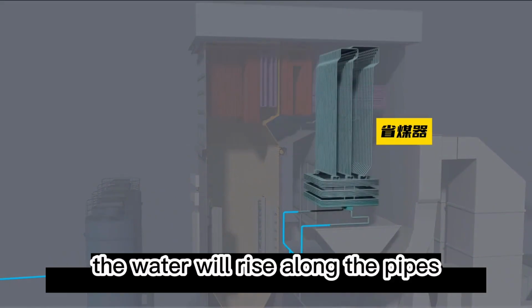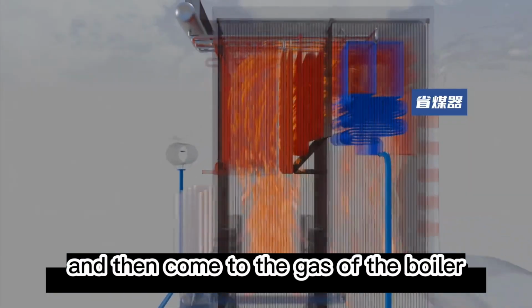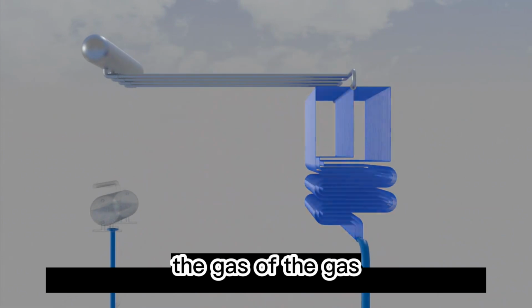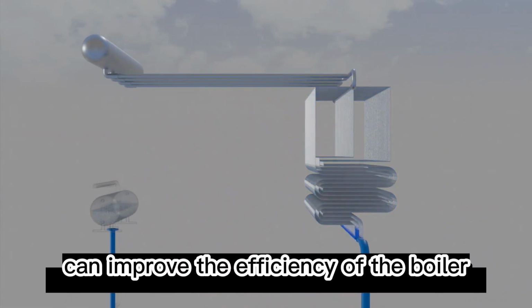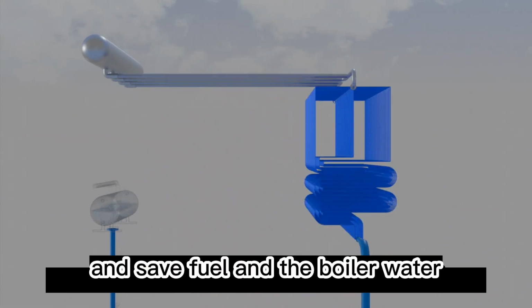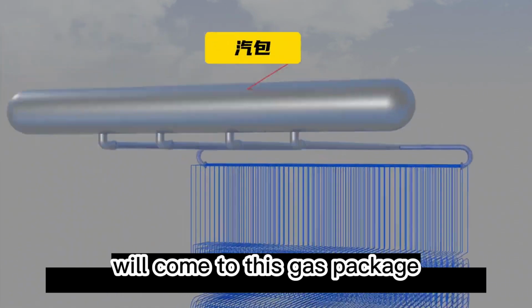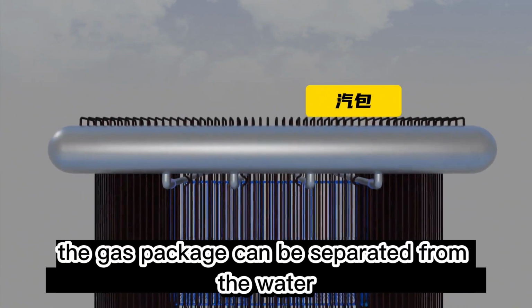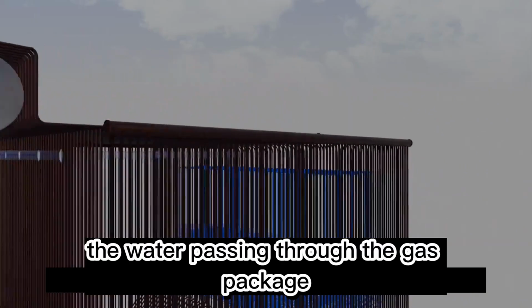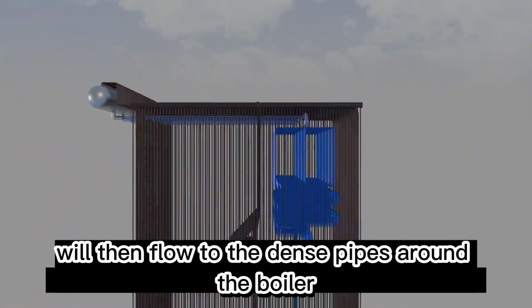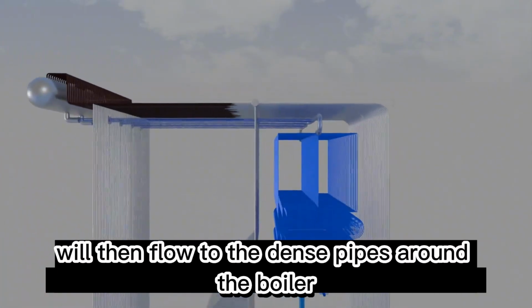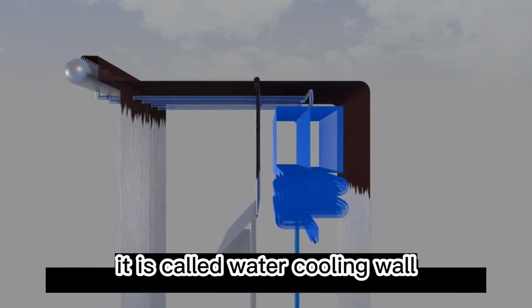The water will rise along the pipes and then come to the economizer of the boiler. The economizer can improve the efficiency of the boiler and save fuel. Then the boiler water will come to this steam drum. The steam drum can separate steam from the water. The water passing through the steam drum will then flow to the dense pipes around the boiler. It is called the water cooling wall.